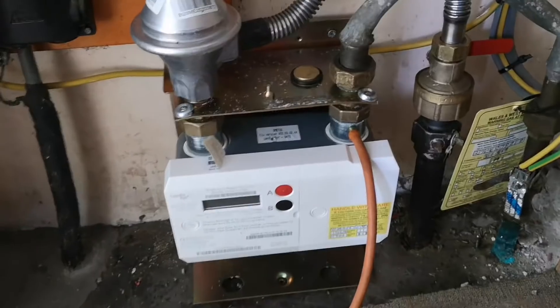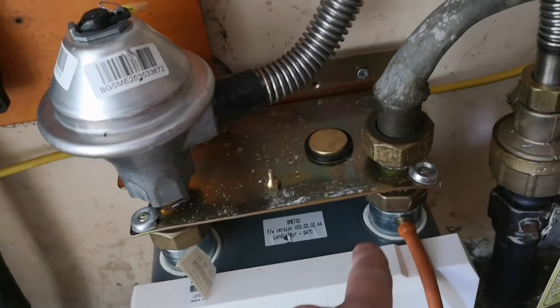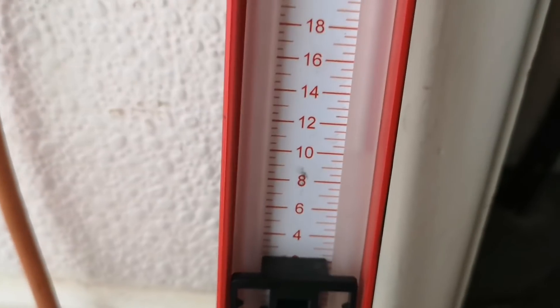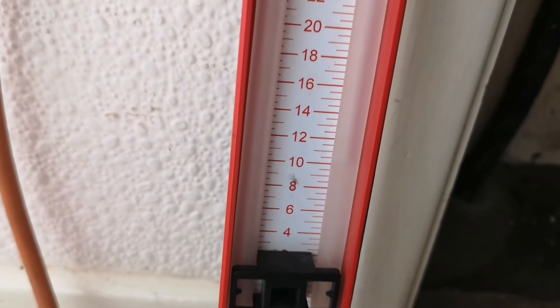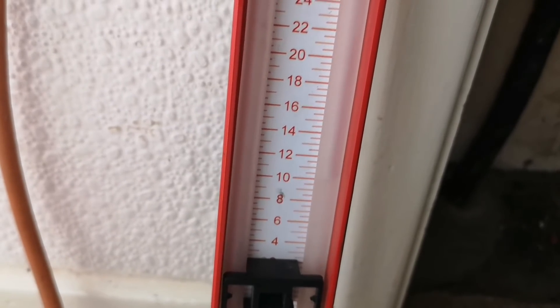The first thing we're going to do is remove the utility supplier's blank disc from the meter, hook the meter up to the test gauge, then pressurize the gas pipework and put a test on. The first thing we do is a let-by test, which tests if the emergency control valve - this thing here - is passing. We gas it up to around 10 millibar, then wait a minute, and if we record a perceptible rise we know the ECV is passing.